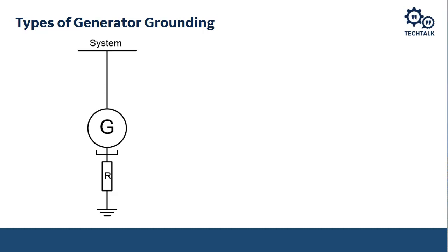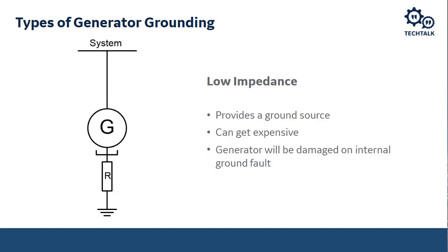fault currents typically in a range of 400, 600 amps, in that range. Even less, maybe 200 to 400 amps. So in summary, the low impedance provides the ground source, can get expensive because of the selection of the rating of the resistors, and the generator will be permanently damaged on an internal ground fault.